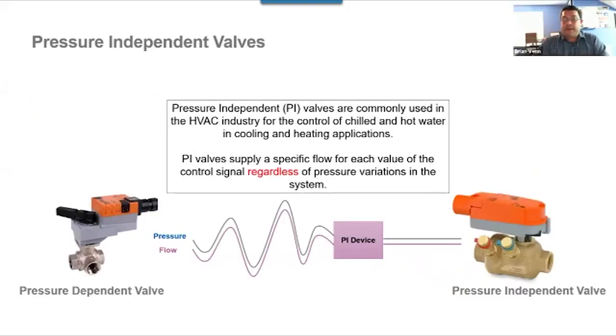And Bob, from a TAB standpoint, the maximum amount of pressure that we need or want is only enough to get the GPM we want, because our job is to get the pumps running as low as possible for the owner's energy recognition of their design. Exactly. Pump energy equals dollars. So it's a consideration, but it's not that I need more pump head. I know I was on jobs in the beginning of this, when we started with PI valves, I think, as I said, in '03, where we didn't have 5 pounds out there, but the pumps were set so low by direction of design that even standard control valves weren't going to accomplish much because there was no pressure drop.